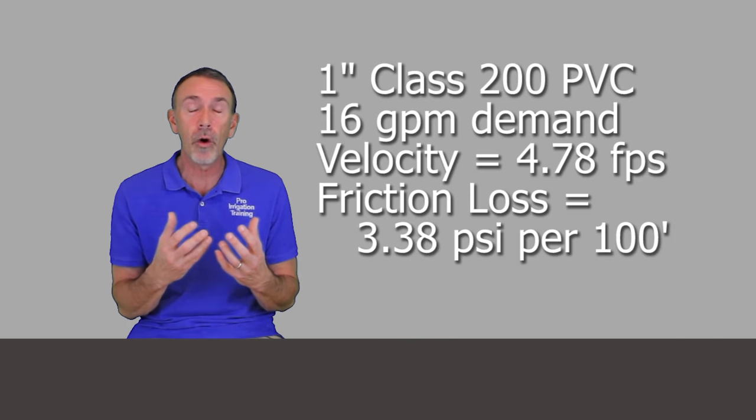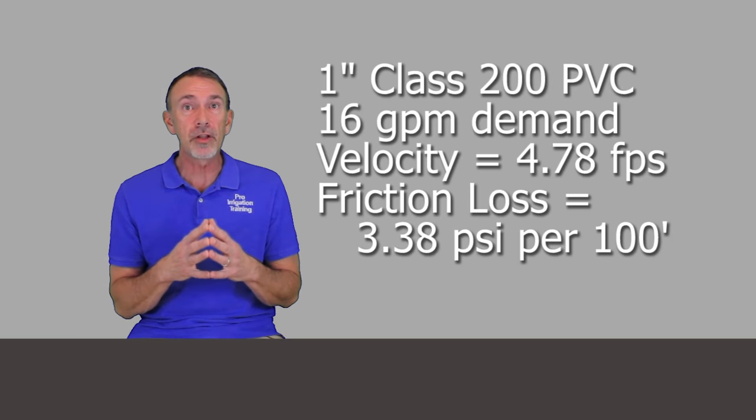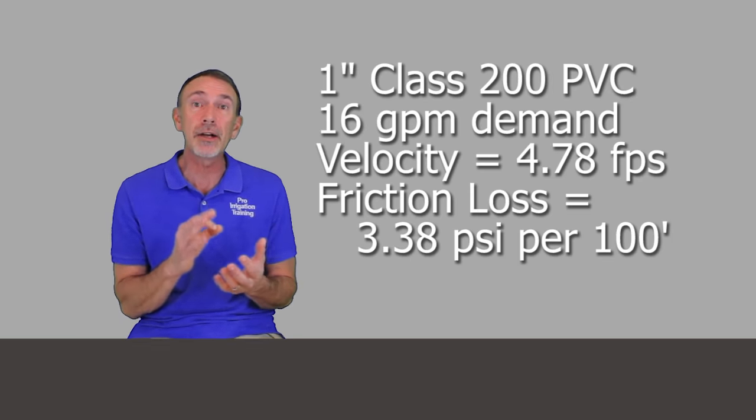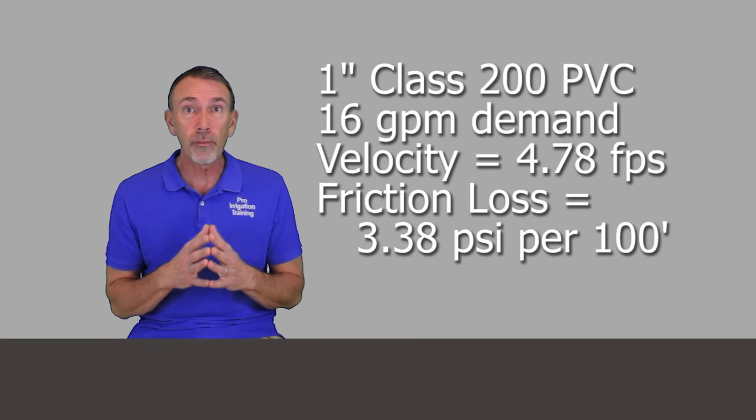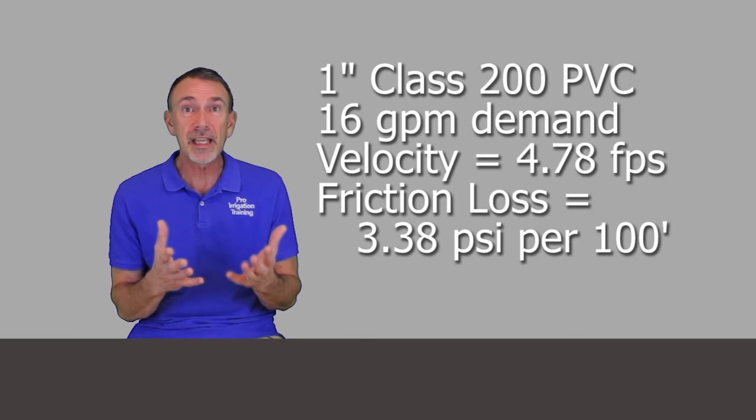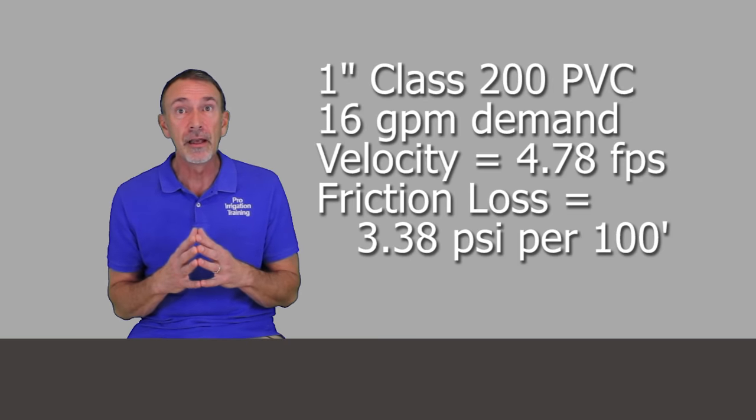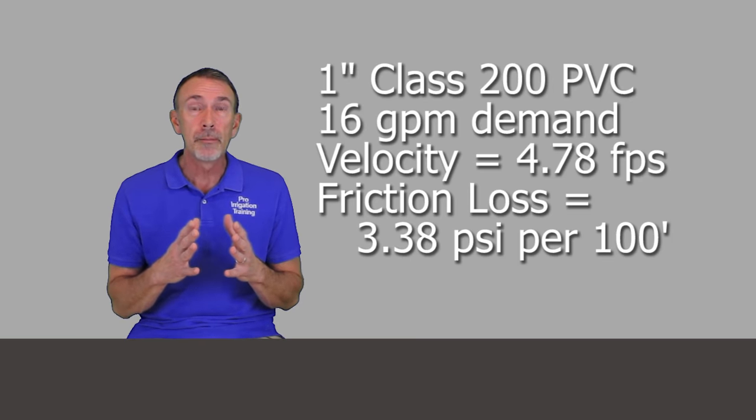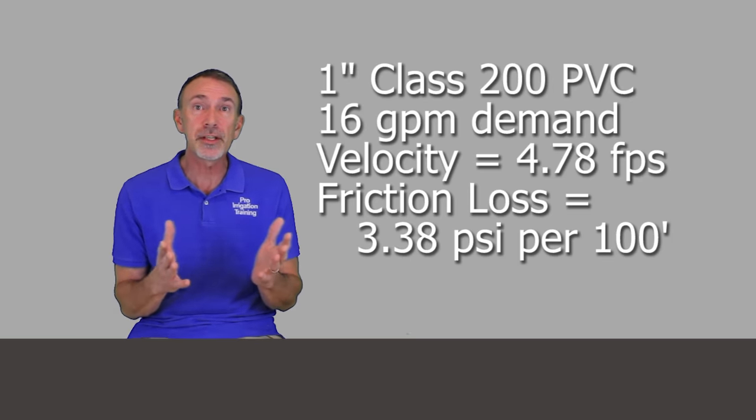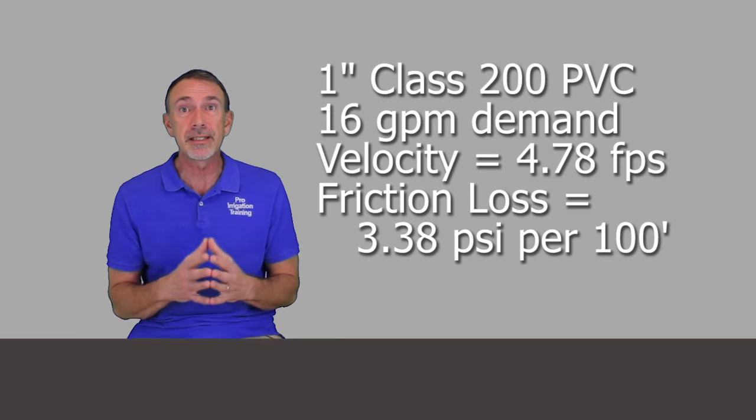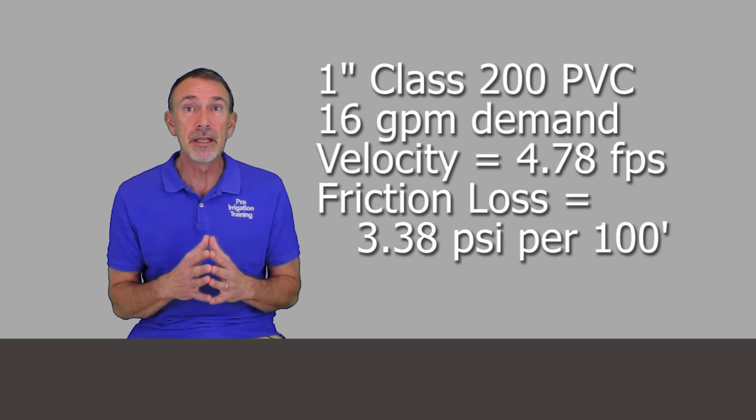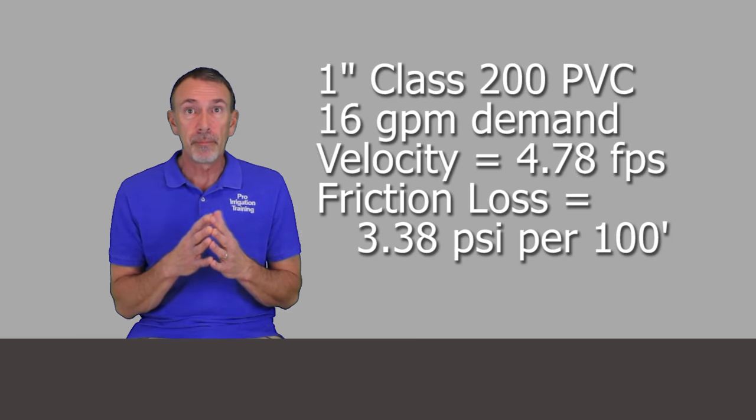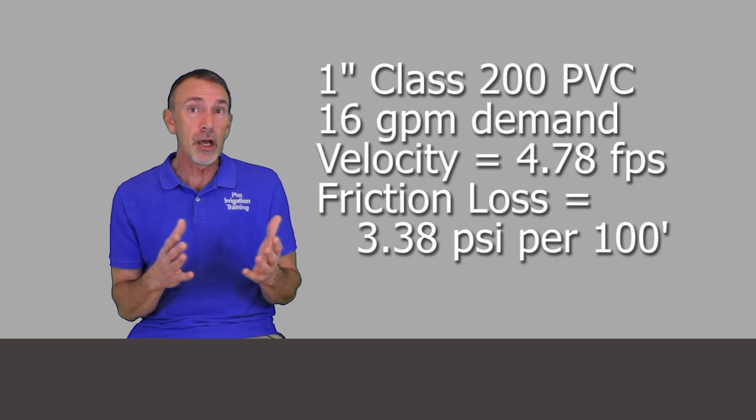For 16 gallons per minute in a one inch piece of class 200 PVC pipe, that's the thin walled irrigation pipe, the velocity of that is 4.78 feet per second. With PVC pipe we want to keep it below five feet per second and above that the friction loss starts to increase exponentially. Our friction loss per 100 feet of pipe is 3.38 pounds per square inch per hundred feet of pipe.